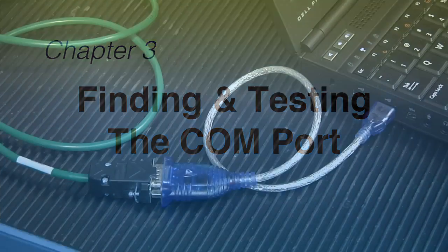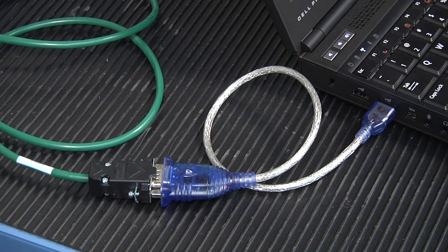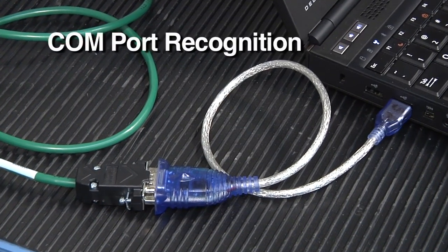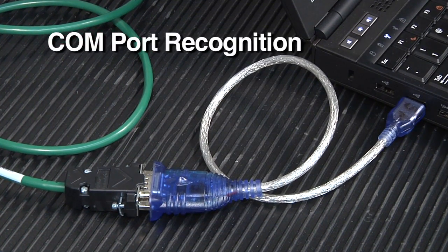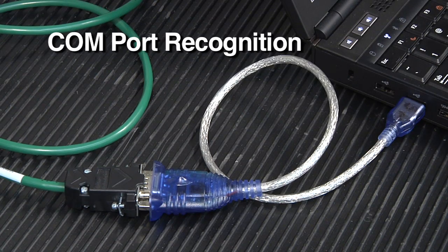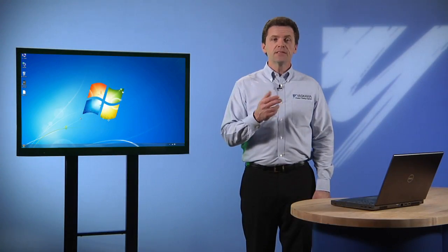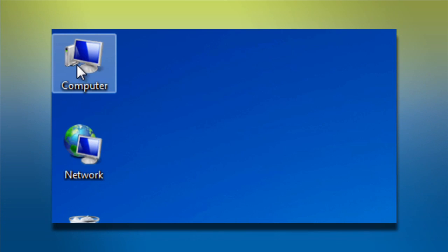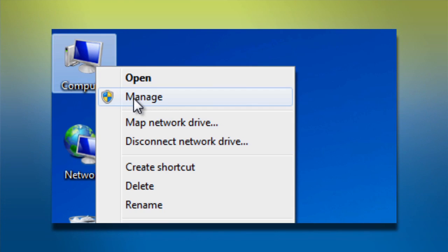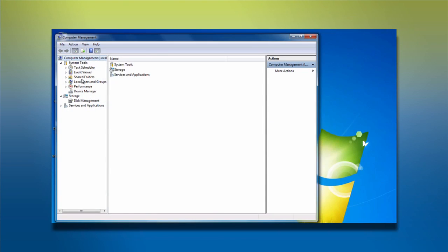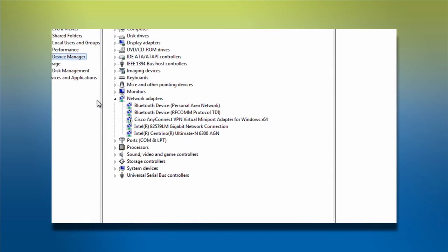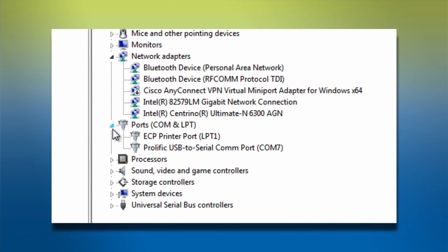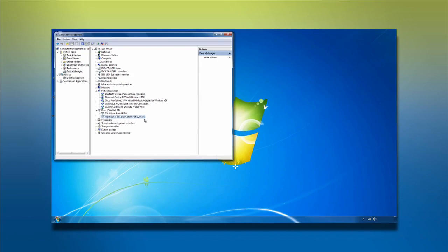But, before we do, it's very important to make sure that DriveWizard recognizes the COM port on your computer that we're using to communicate with the drive. The easiest way to accomplish this is to load the device manager in Microsoft Windows and check to see what COM port your computer is using to communicate with the Yaskawa drive. This is also a good way to verify proper driver installation if you are using a USB adapter.